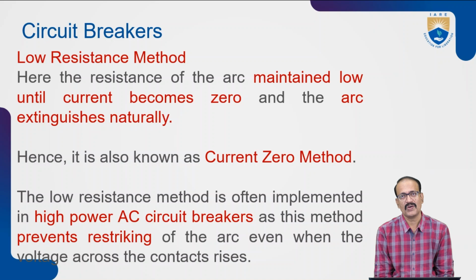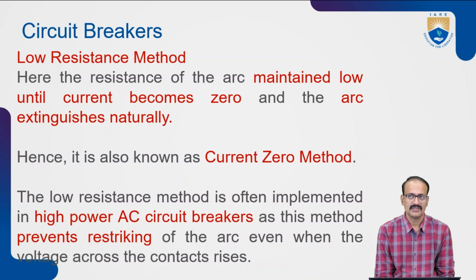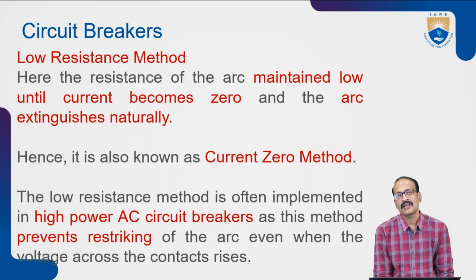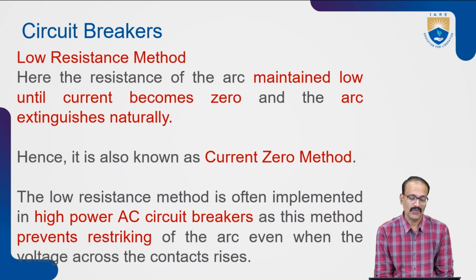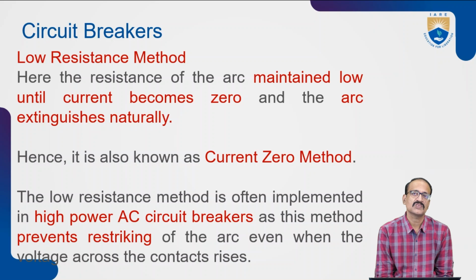because in low power AC circuit breakers we are using high resistance. If we were using high resistance in high power circuit breakers, imagine how much heat would be produced. That's why we are using the low resistance method in high power, and the high resistance method in low power AC circuit breakers. And it also prevents the restriking of the arc even when the voltage across the contacts rises. So due to this method, the restriking problem is also solved.